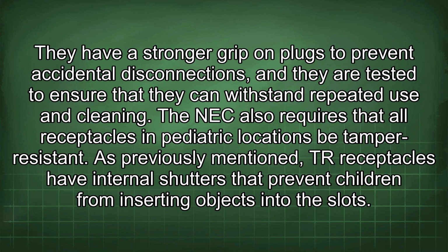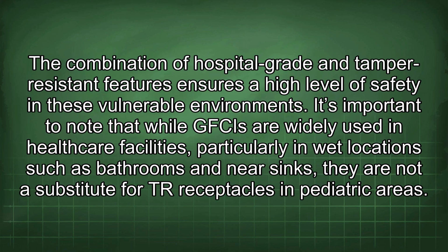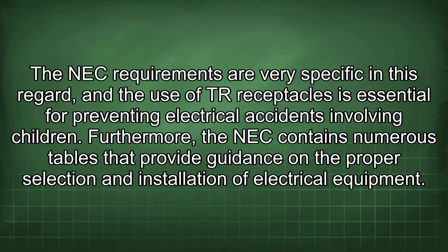The NEC also requires that all receptacles in pediatric locations be tamper-resistant. As previously mentioned, TR receptacles have internal shutters that prevent children from inserting objects into the slots. The combination of hospital-grade and tamper-resistant features ensures a high level of safety in these vulnerable environments. It's important to note that while GFCIs are widely used in healthcare facilities, particularly in wet locations such as bathrooms and near sinks, they are not a substitute for TR receptacles in pediatric areas.